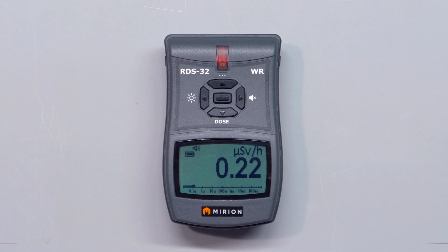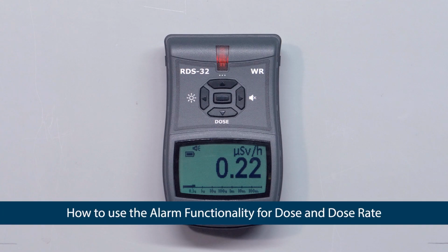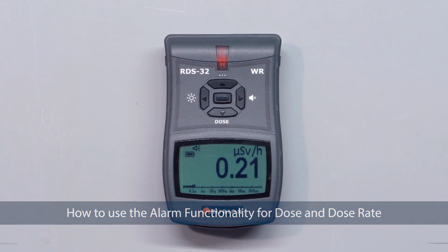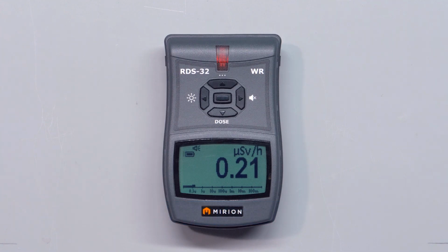The RDS-32 features dual alarm functionality for dose and dose rate. The dual alarm enables setting a lower warning level in addition to the alarm level. The following example covers dose rate alarm settings for a meter with sievert units. Remember that the RDS-32 is also available in REM units.